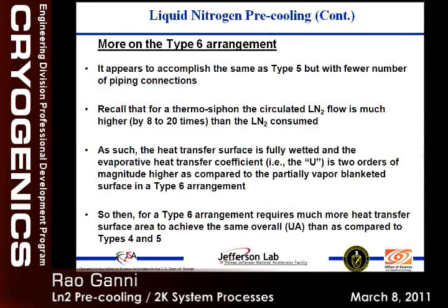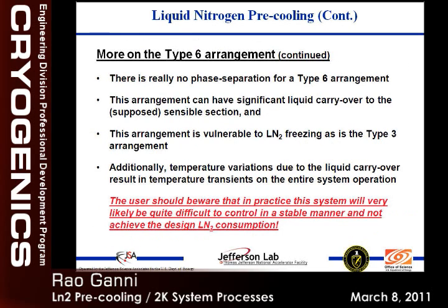The type 6 arrangement was interesting because when I was writing it, we were going through the SNS commissioning. We had a lot of discussions with folks, the vendor Linde, but they were convinced there was no difference between type 6 and the other, because I didn't have this analysis completely done by the time. Then when we built it, we figured out that it's not exactly the same, because of what happens when we go back.